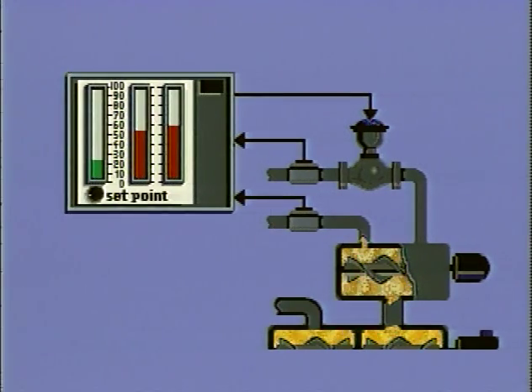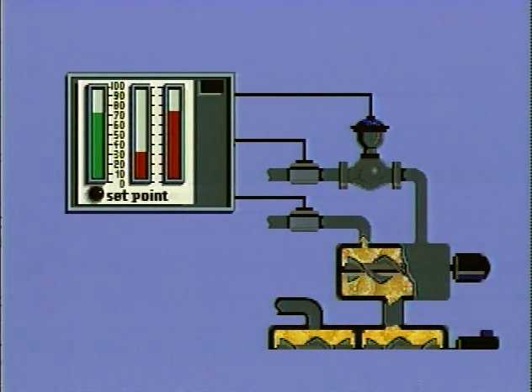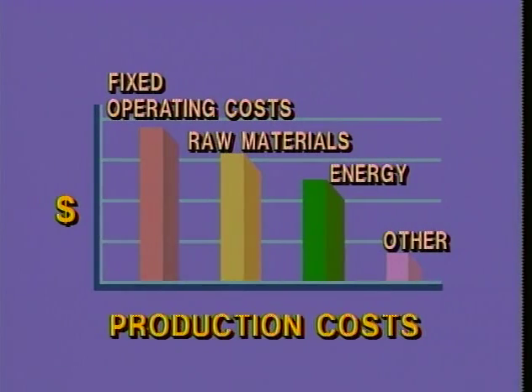Here is how ratio control worked in the chemical plant. The flow of ingredient 2 into the process was continuous but variable. The flow of ingredient 1, however, was carefully controlled so that its flow was always half that of ingredient 2. For the ratio to be controlled, it really didn't matter what the absolute flow rate of the materials into the process was. It only mattered that this 2-to-1 ratio was always maintained. The addition of the new ratio controller and an additional pipeline was not a very costly modification to the plant, and soon the company was enjoying the benefits of reduced materials costs.